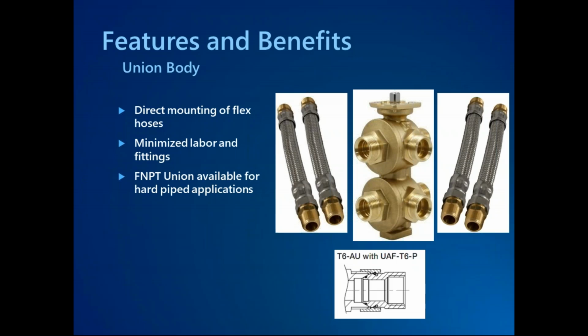As we mentioned earlier, there are these union body designs out there. They can be just straight unions with fittings that go to FNPT to allow service and troubleshooting in the field, or you can tie in flex hoses directly to all of these ports. So we've seen some jobs out in the field that always remind me of the old screensaver from the 90s, the pipe screensaver, where we're trying to tie these 6 different connections into a very small space. We'll look at some other solutions on how to do this efficiently a little bit later on, but one option is definitely to include flex hoses and simply to mount the 6-way up in the plenum on a piece of unistrut and make up any of these additional offsets that could give you headaches if you're trying to hard pipe it with flex hoses.